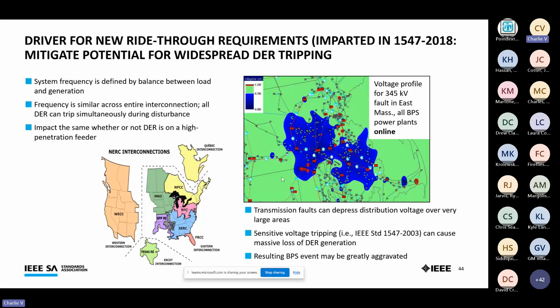What's going on? So this is looking forward. The P1547 revision is active. My opinion at this time is it's mainly cleanup to deal with a couple errors in 1547-2018, and a lot of focus on cleaning up the testing requirements, so the 1547.1 test procedure and UL 1741 certification processes can be adjusted a little bit to remove some unintended complexity. There's also a 1547 guide for intentional islanding, i.e. microgrids.